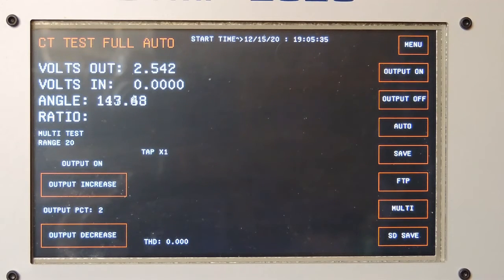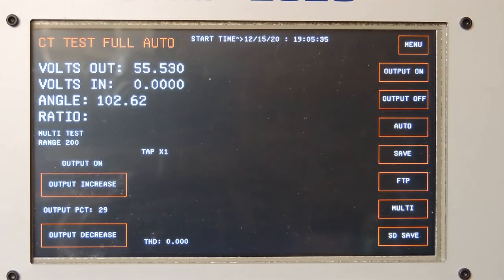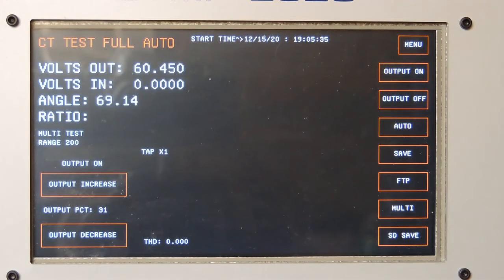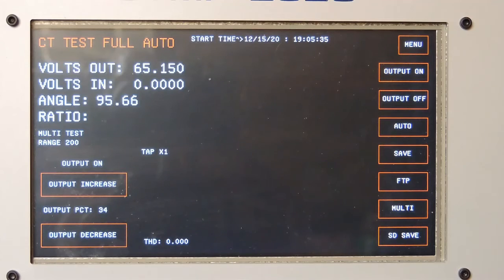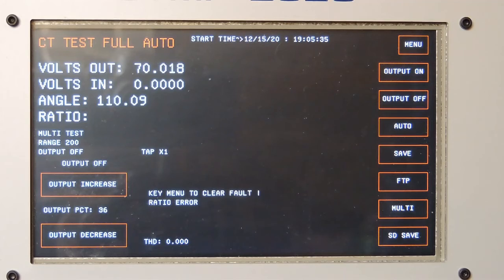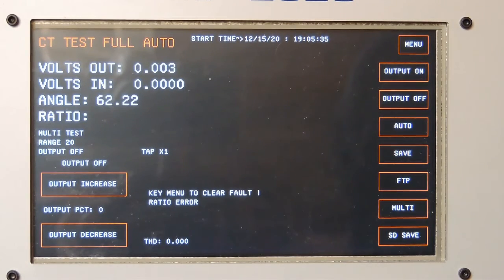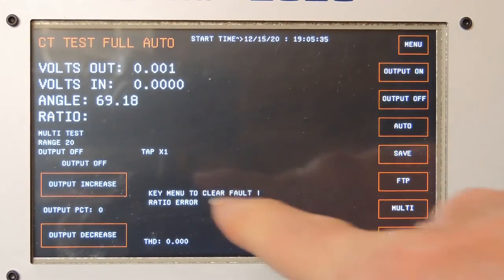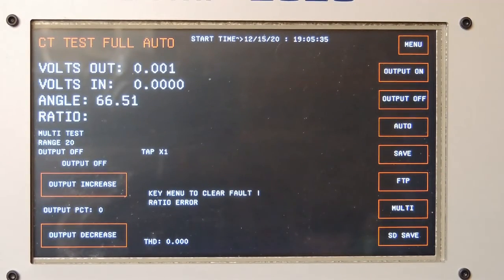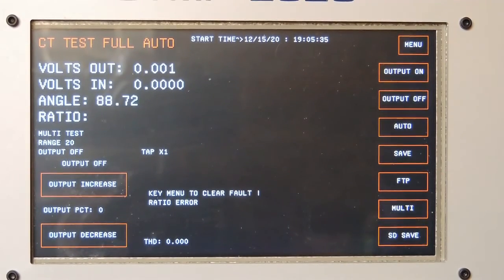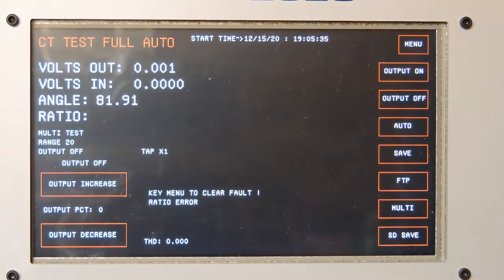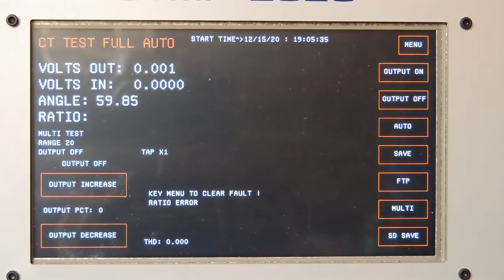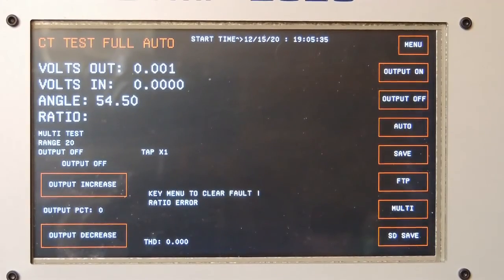Ramping up the volts out. It says key menu to clear fault. It says ratio error. It was not getting a ratio in range, so it flagged that. And that's the what-if the CT is actually not connected.